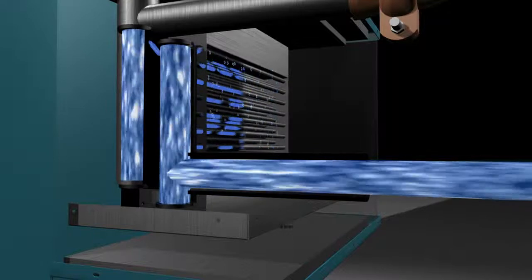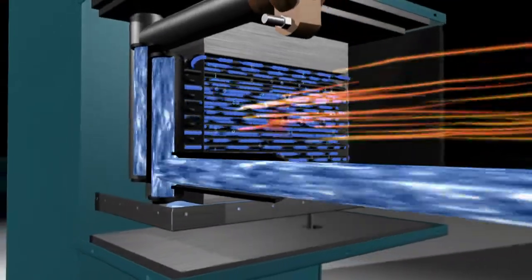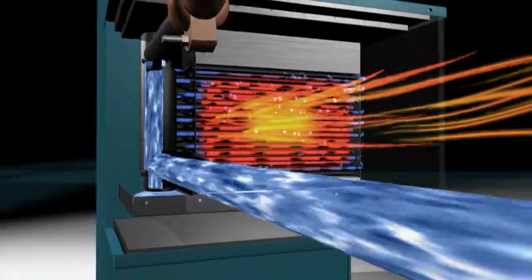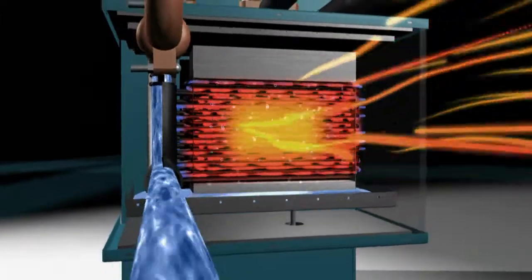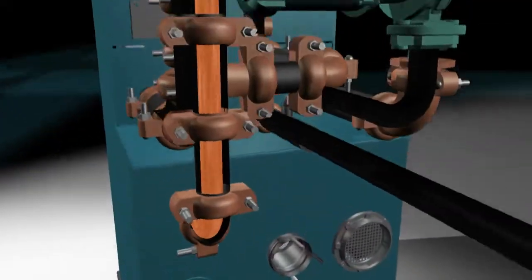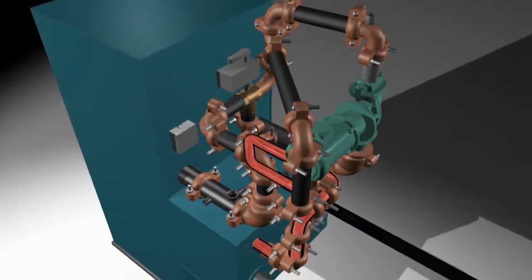Thermal Solutions uses hot flue gas, the discharged byproducts of gas combustion, to pass through the fins and heat water flowing in the tubes. This preheated water then enters the mixing loop, where it is blended into the primary heat exchanger for more heat, or supplied to the system to satisfy heating demand.